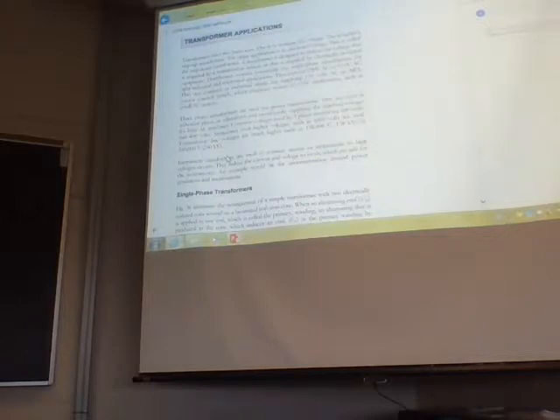A transformer is designed to deliver the voltage that is required by a transmission system or by electrically powered equipment. Distribution systems commonly use single-phase transformers for light industrial and residential applications. They can convert 220 volts to 110 volts. They're common in industrial plants, supplying 110 volt AC to motor control panels, which distribute power to 110 volt applications, such as small AC motors.